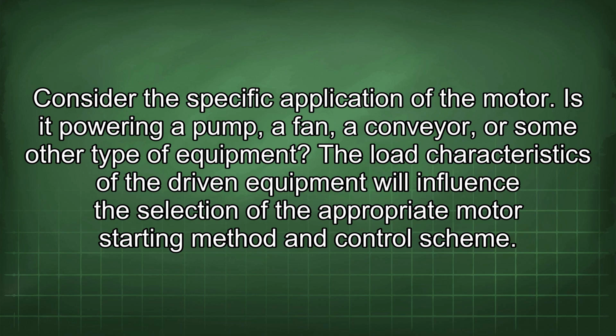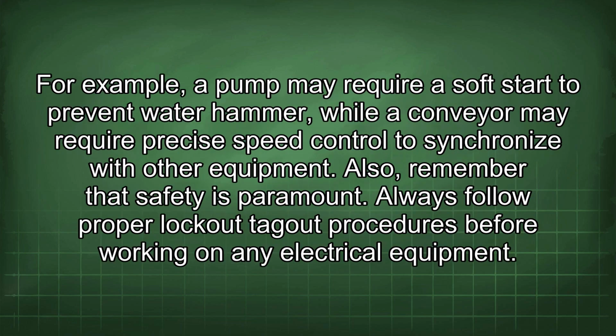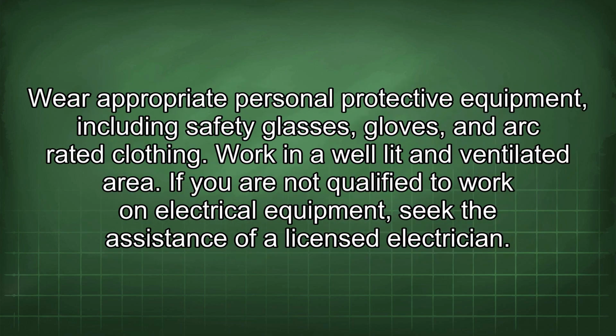The load characteristics of the driven equipment will influence the selection of the appropriate motor starting method and control scheme. For example, a pump may require a soft start to prevent water hammer, while a conveyor may require precise speed control to synchronize with other equipment. Also, remember that safety is paramount. Always follow proper lockout-tagout procedures before working on any electrical equipment. Wear appropriate personal protective equipment, including safety glasses, gloves, and arc-rated clothing. Work in a well-lit and ventilated area. If you are not qualified to work on electrical equipment, seek the assistance of a licensed electrician.